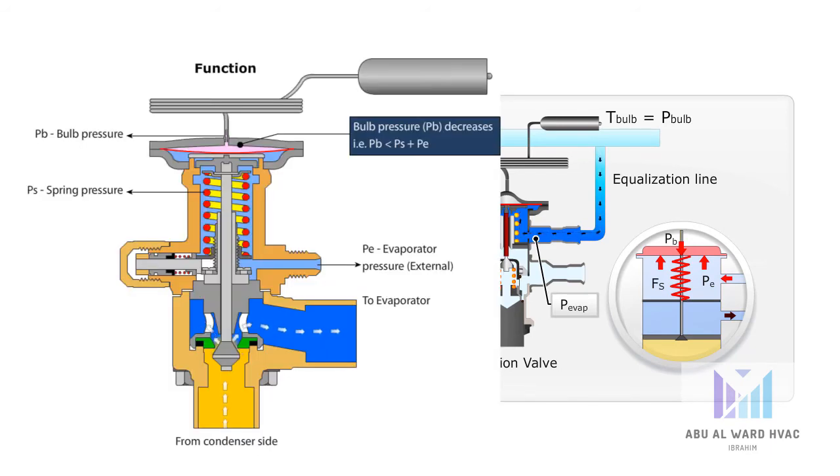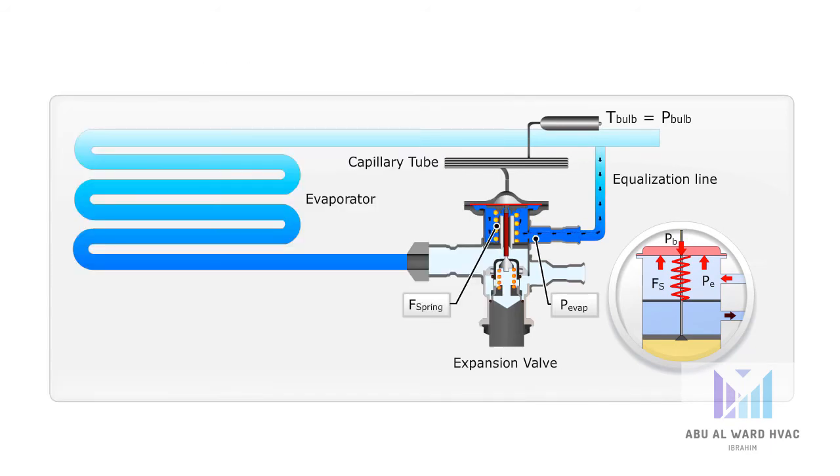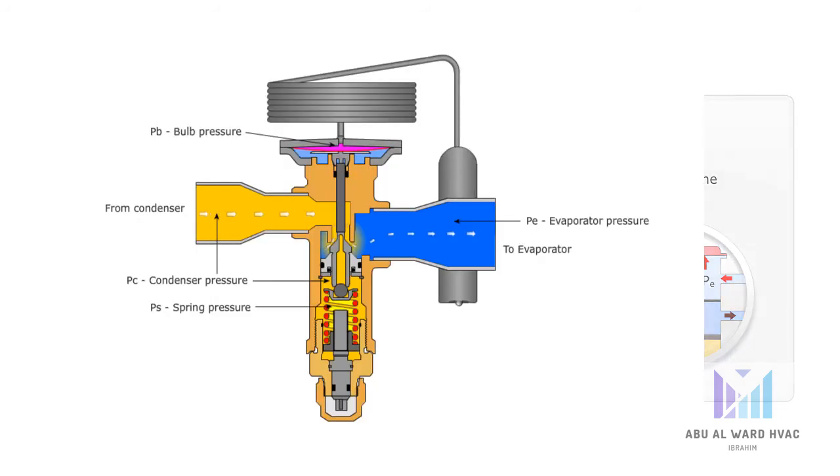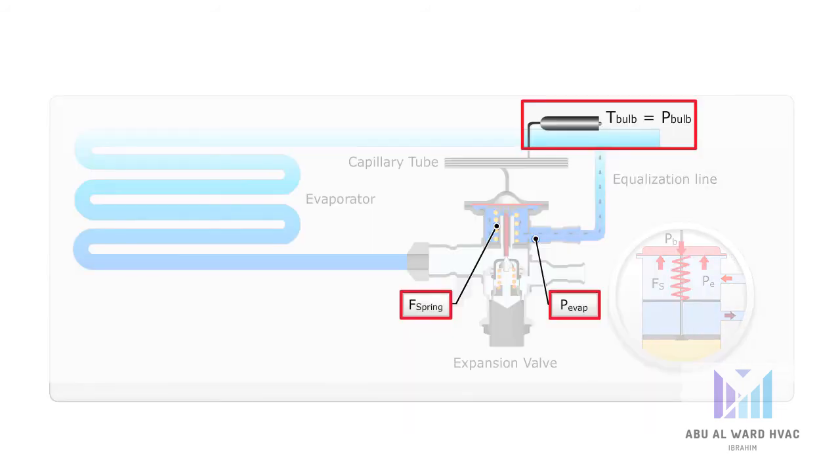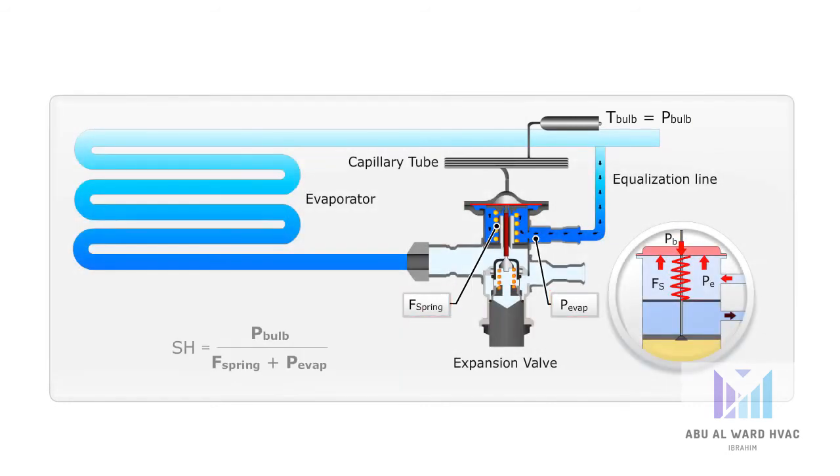Together with the valve main spring F-spring, the two pressures achieve a pressure balance which represents the requested superheat or SH at the evaporator outlet. Depending on the actual SH value, the TXV orifice will open or close.